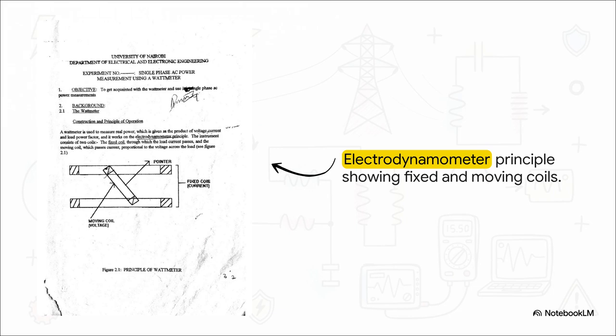These work on the electrodynamometer principle, and the internal mechanics are just fascinating. Inside, you've got a fixed current coil connected in series with the load, and a moving voltage, or pressure, coil connected in parallel. As power flows, their interacting magnetic fields physically push a pointer across a dial to show you the real power being consumed.